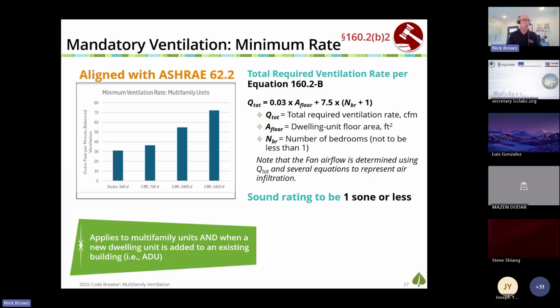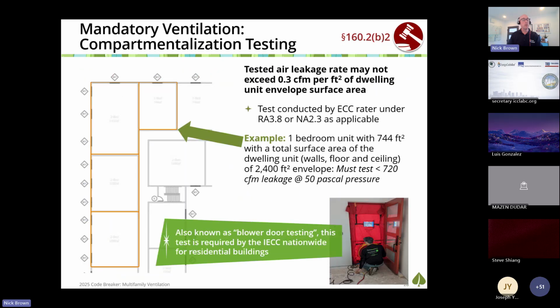Also required is a maximum 1 sone of sound. This, by the way, will also apply if you're adding a multifamily dwelling unit onto an existing multifamily building. So the compartmentalization testing, which I just said in the last code cycle was required only if you had exhaust ventilation, not required if you had supply or balance, well, now becomes a requirement no matter what method you have, mandatory requirement. And so, for instance, this one bedroom unit shown in this floor plan here, 744 square feet, would have a total surface area of roughly 2,400 square feet of envelope, walls, floor, and ceiling. So to come in under the 0.3 CFM per square foot, we'd need to come in at about 720 CFM of air leakage using the blower door test.